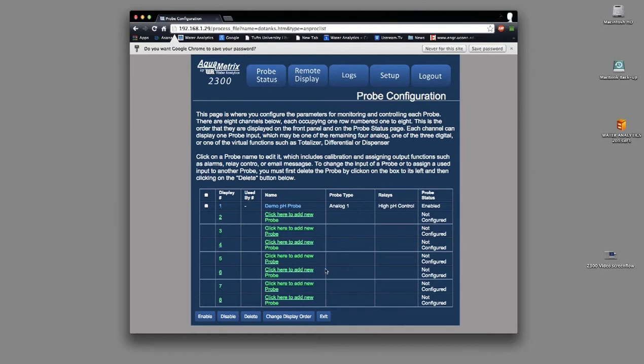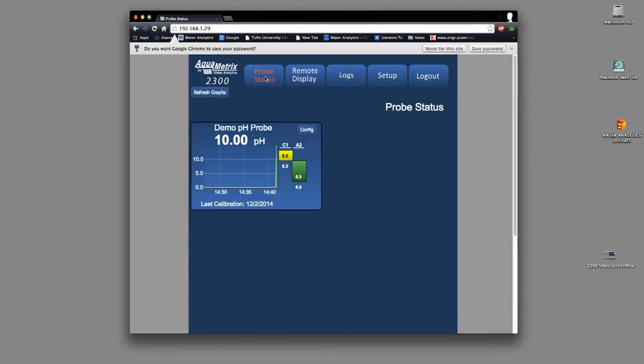And I'm back on the probe configuration screen. I can add another probe and set that one up as well. But I'm good for now, so I'll click on the probe status button on the top menu. Now my pH probe is up and running. It's reassuring to see that it's still reading pH 10, which is the pH of my second calibration solution. Anytime I want to check, all I have to do is reload the IP address right up here, 192.168.1.29, right into my web browser.